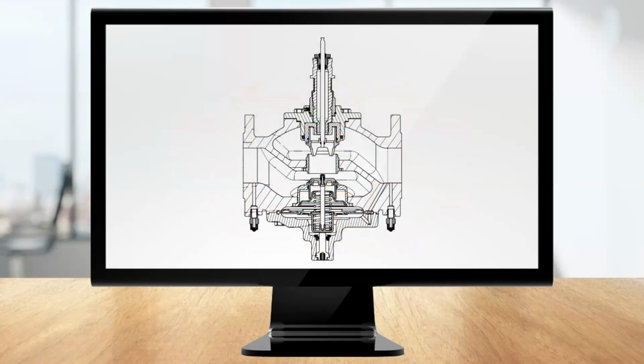Here's a pressure-independent valve from another manufacturer. It looks quite different, but it actually works the same way. Flow goes left to right in this valve. The control valve portion goes up and down; it's a plug. And the regulator sits at the base of the product and works the opposite side of the same seat as the control valve. Pressure is sampled by the regulator from the outlet of the valve, which gets the needed pressure differential to activate the regulator. So although it looks quite different from the previous valve, it gains pressure independence the exact same way.